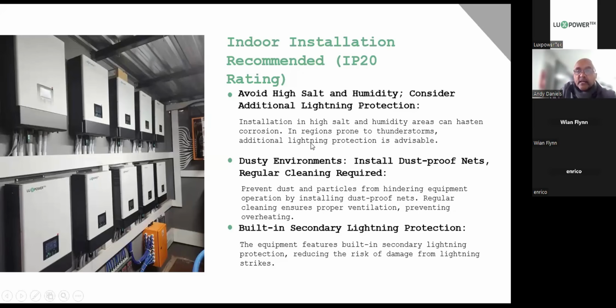The installer will make sure that the room is dry and less humid. Okay, the other thing that we're also going to be avoiding is a dusty environment. If you have a look at this photograph here, you'll see on the side and underneath the machine, there are dust covers that are pre-installed. You've got to make sure that those are in place, and especially encourage your clients to regularly unscrew them. There's a little foam sheet inside there. It's expanded foam. Just take it out, give it a wash, blow it with compressed air, and clean out the dust, put it back in.